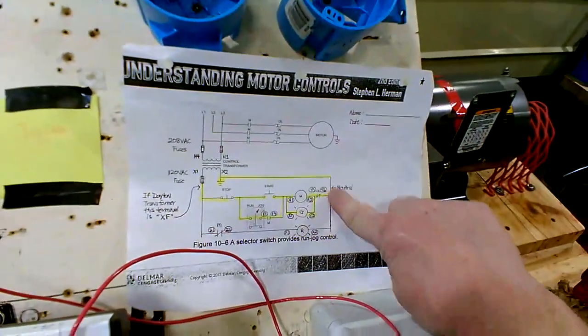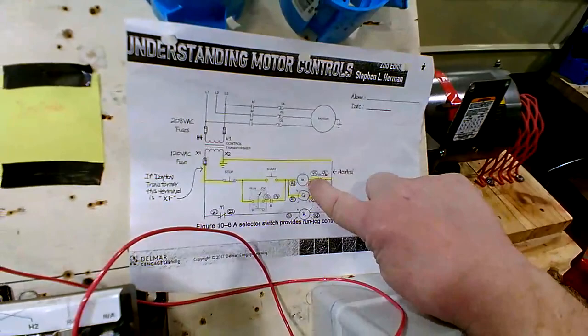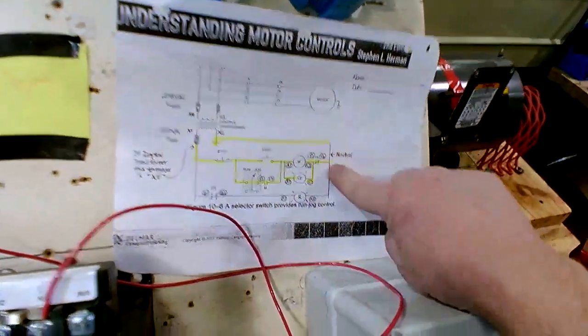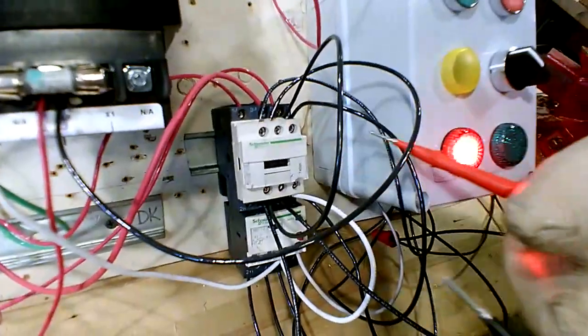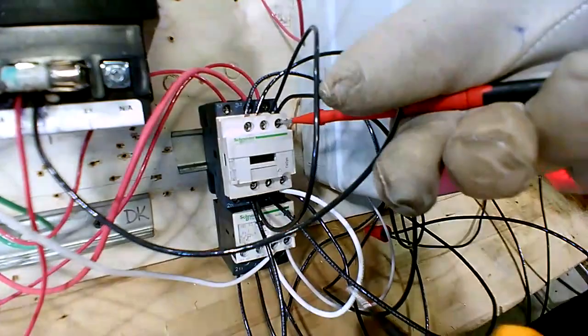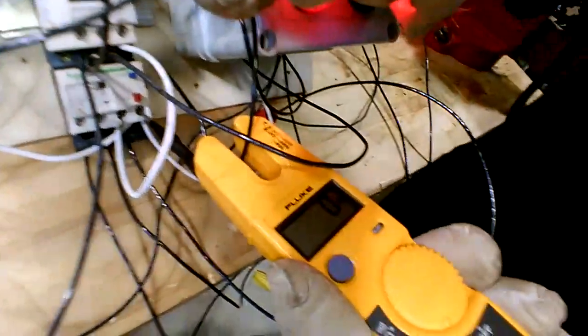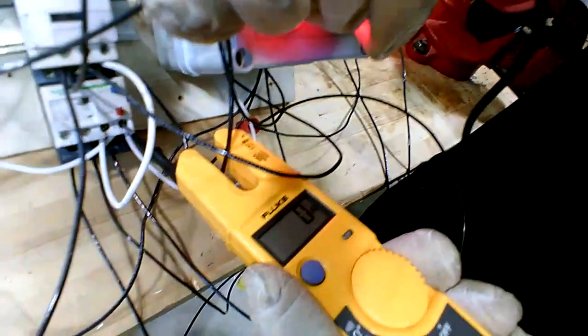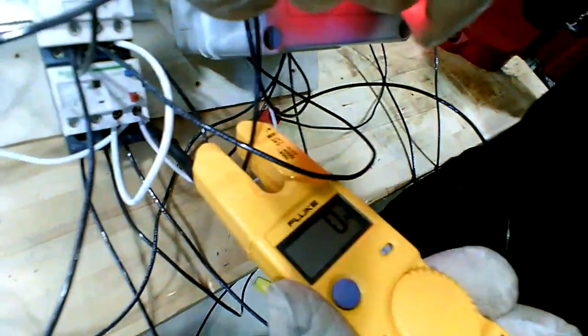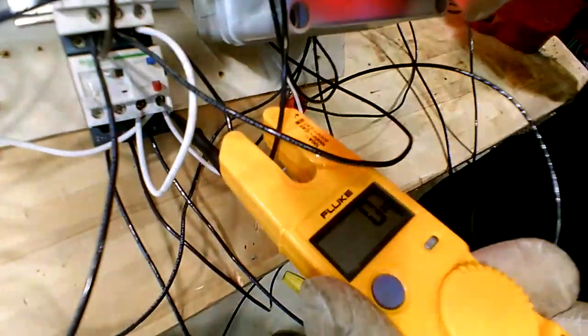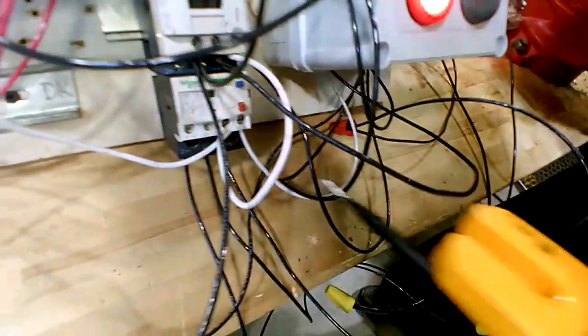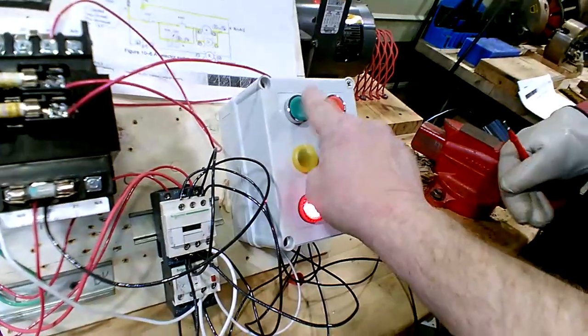Now let's measure from A1 over to the real neutral at 96. So go A1 and 96, and we're going to see if that overload may be opened up. So you're checking A1, and then you're going to check the 96 there. I'm going to hit the start button. And what do you see? Nothing. So what that means is you're missing the signal here from the start button.